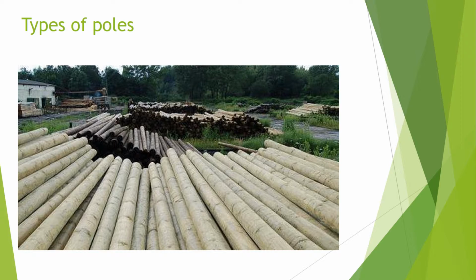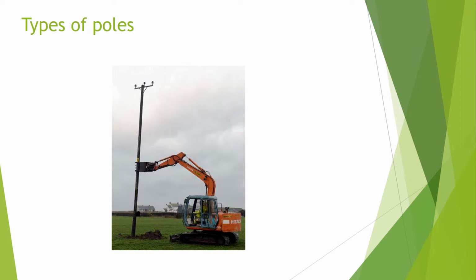The height and diameter of the poles will vary according to factors such as required ground clearance and conductor voltage and cross-sectional area. The poles are sited in holes of depths that vary depending on pole height. Poles of up to 10 metres in height are set into holes of at least 5 foot deep, whilst poles over 10 metres high must be set into holes that are at least 6 foot deep. Once a pole being installed is level and fully aligned, a block of wood, generally a section of railway sleeper, is attached to the pole below ground, which helps to stabilise the pole in high winds. The hole is completely backfilled, usually with a concrete-like material such as permasoil added for extra stability.